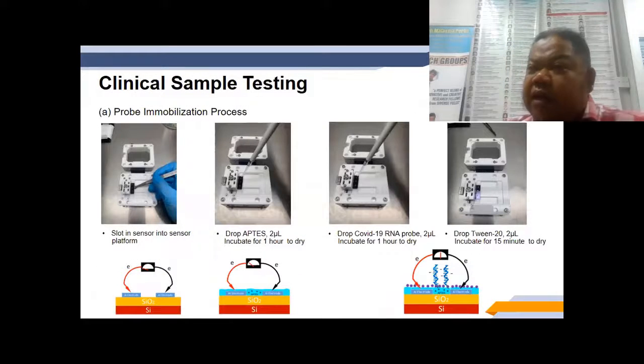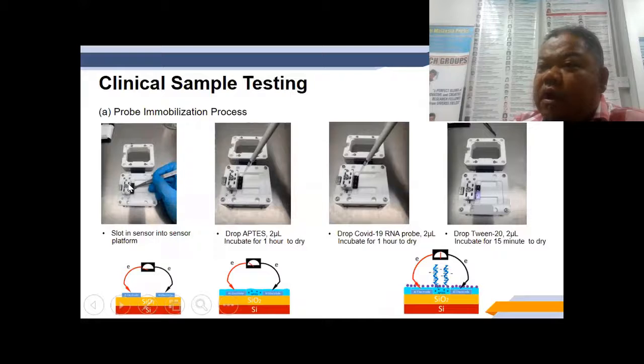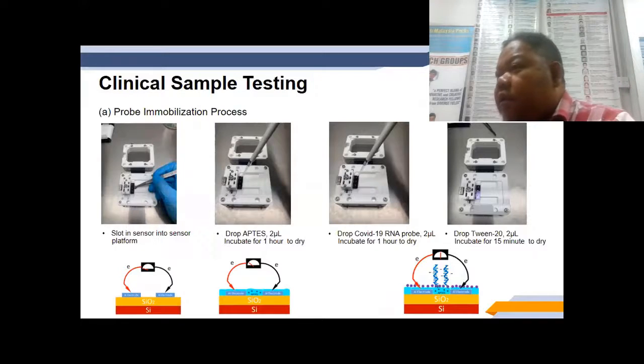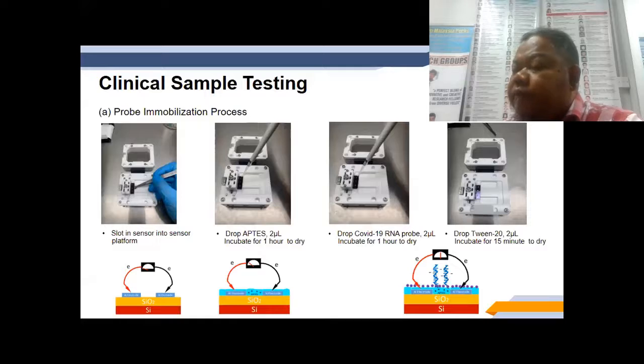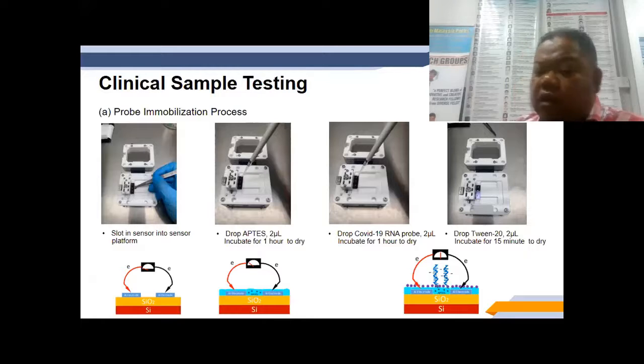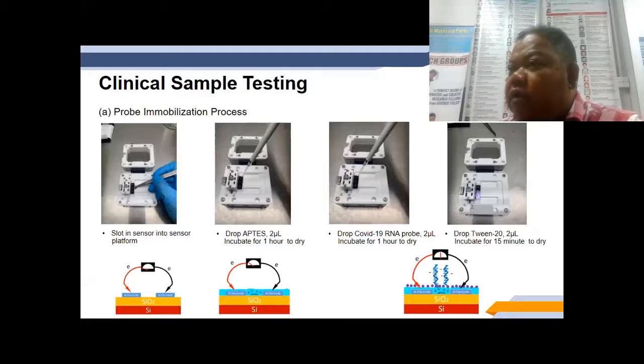So this is clinical sample testing. So how is this analysis or diagnosis conducted? First of all, I hook this sensor into this holder. I can call it a holder. Okay, and then I start to drop the linker. After I drop the linker, I introduce the probe. Then during the clinical testing, I have to introduce another step, a blocking agent. I have to block after I introduce the probe. So the excess probe, I will block it. I don't want to see any signal from the excess because it will cause noise to my result. Okay, I will show you two different results. One is without blocking agent, the other one with the blocking agent.